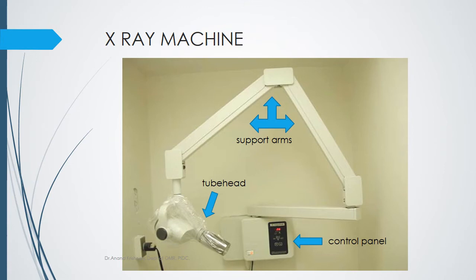This is a typical intraoral machine. It generally consists of a tube head, control panel, and support arms, supplied as either a wall mount or mobile unit. The wall mount is fixed and has a limited area of use. Our college uses a mobile unit with a vertical stand and wheels, which can be mobilized and used in multiple cubicles simultaneously.